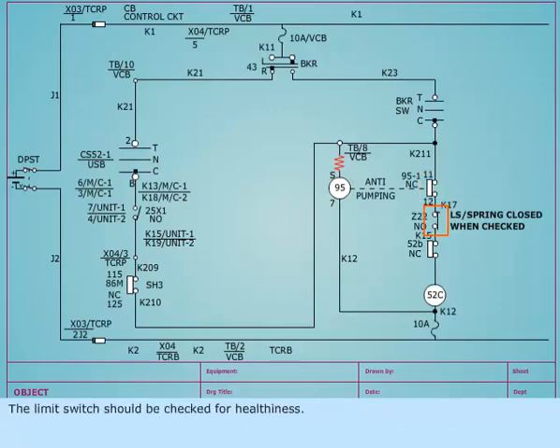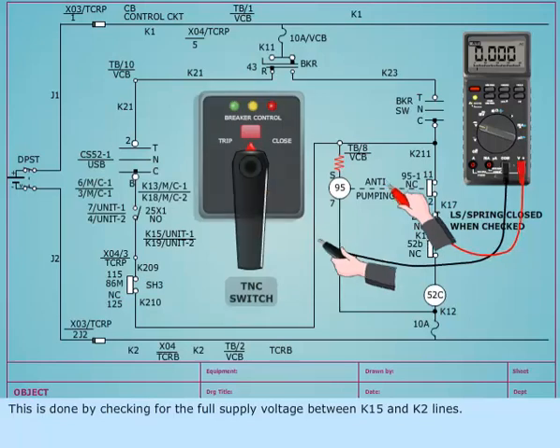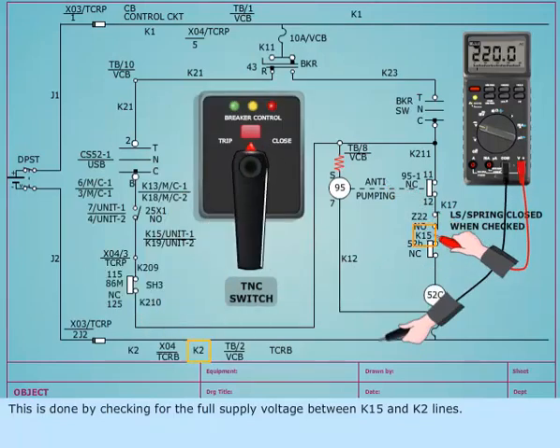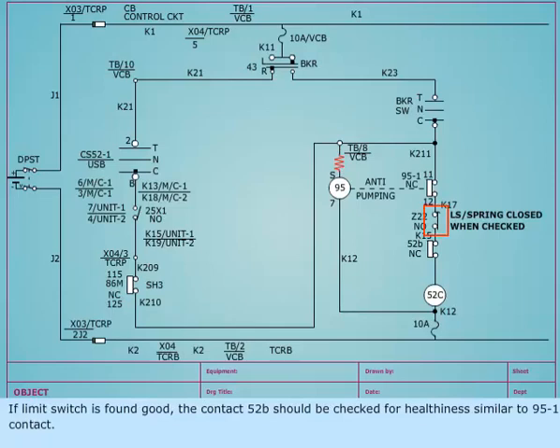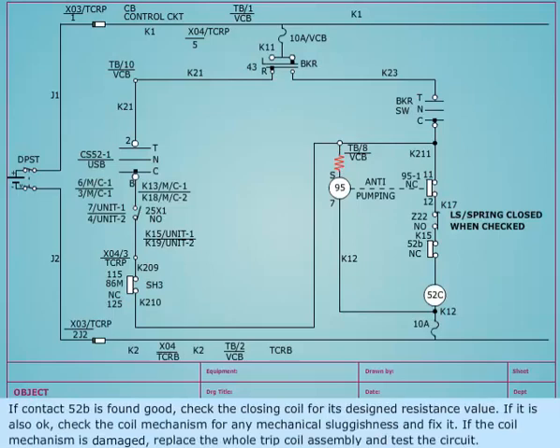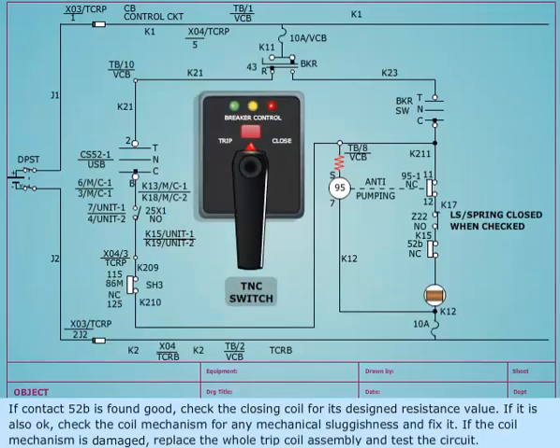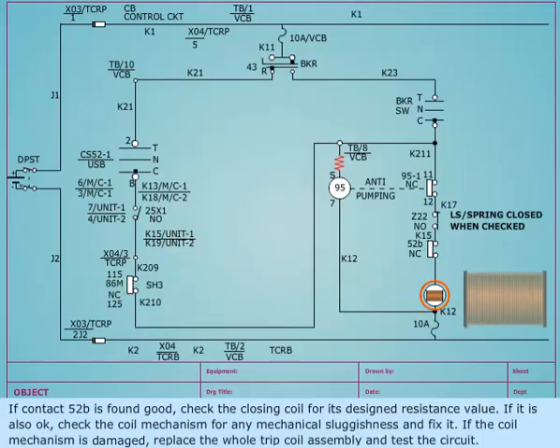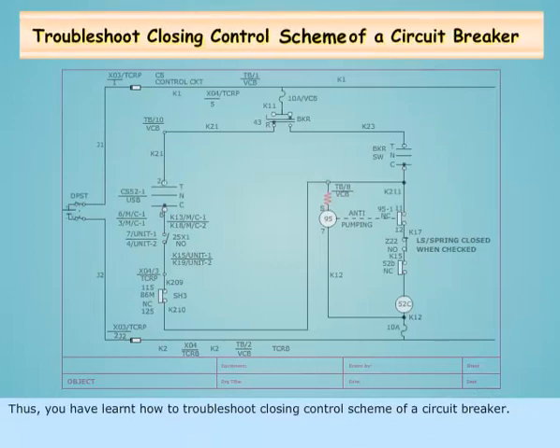The limit switch should be checked for healthiness. This is done by checking for the full supply voltage between K15 and K2 lines. If the limit switch is found good, the contact 52B should be checked for healthiness similar to 95-1 contact. If contact 52B is found good, check the closing coil for its designed resistance value. If it is also okay, check the coil mechanism for any mechanical sluggishness and fix it. If the coil mechanism is damaged, replace the whole trip coil assembly and test the circuit. Thus, you have learned how to troubleshoot closing control scheme of a circuit breaker.